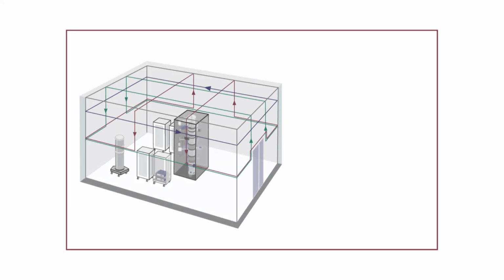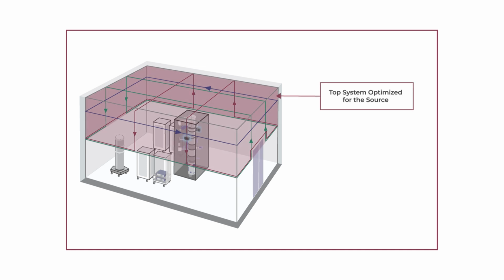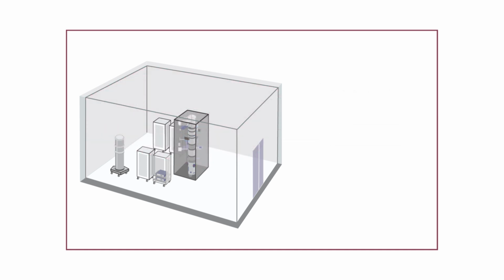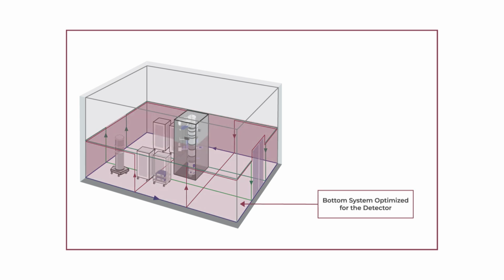So another option, in lieu of shielding or in conjunction with AC magnetic field shielding, is a dual cancellation system. A dual cancellation system solves the problem of field gradients on transmission electron microscopes. Basically, the way it works is you have two independent field cancellation systems that optimize for two different portions of the microscope. You have a top system that optimizes for the top of the electron beam column, typically with the sensor optimization point near the source or somewhere between the source and the sample height. And the second is at the bottom half of the electron beam column, with the sensors optimized for the detector location.